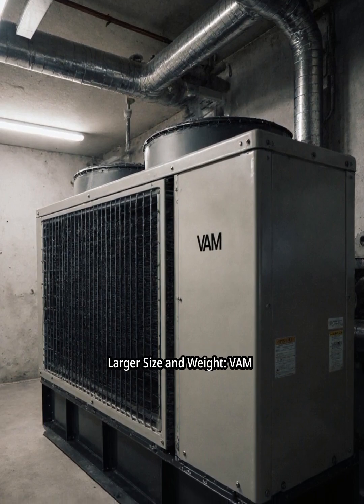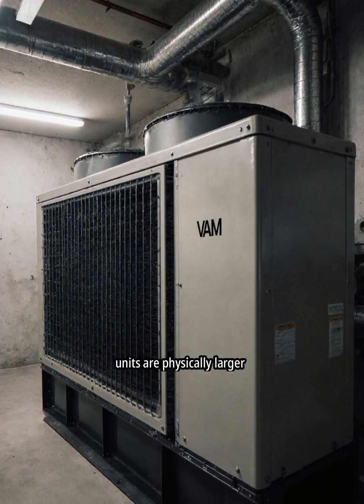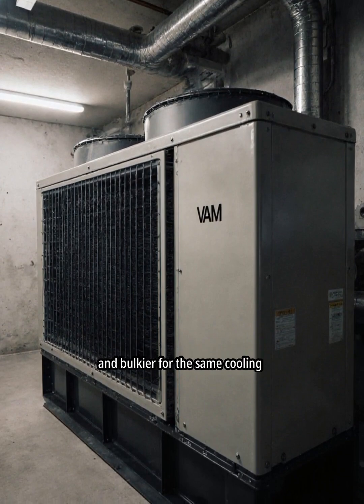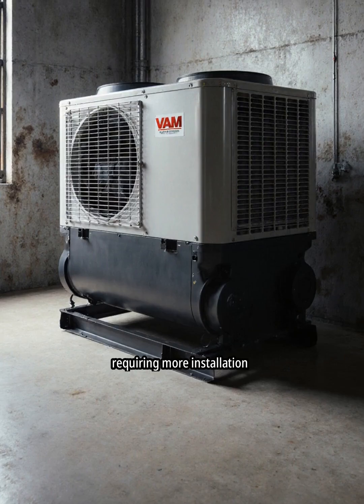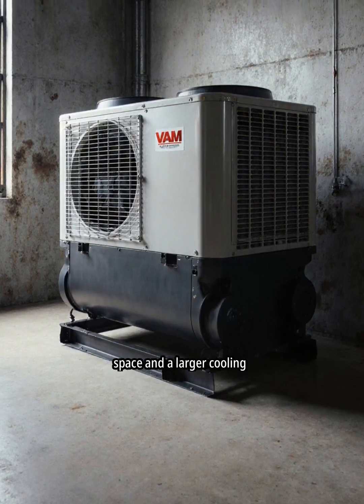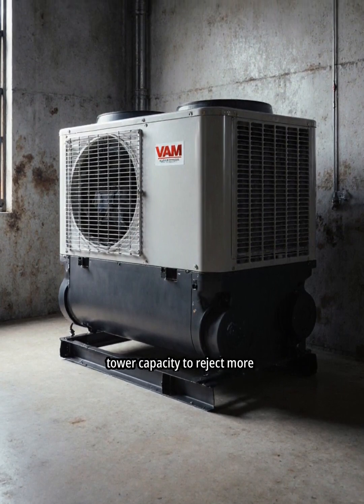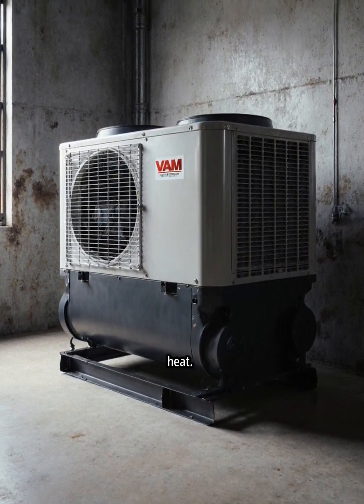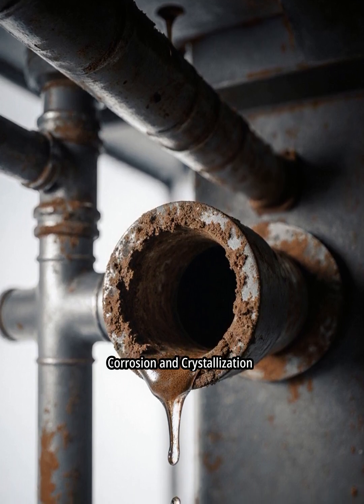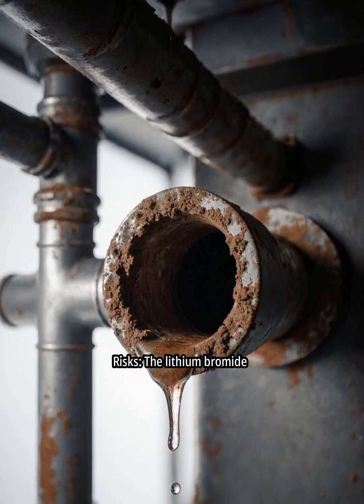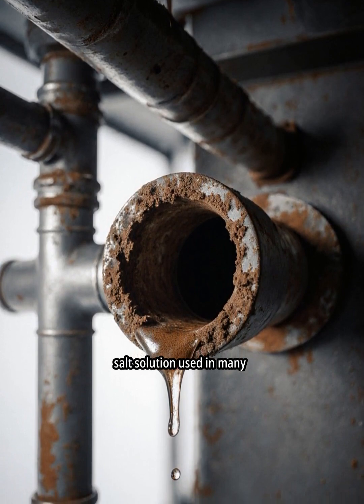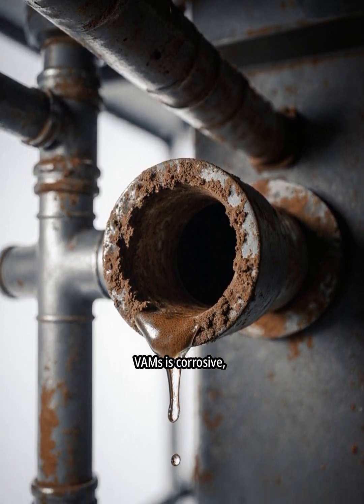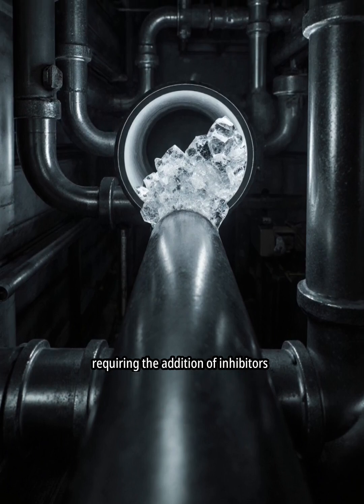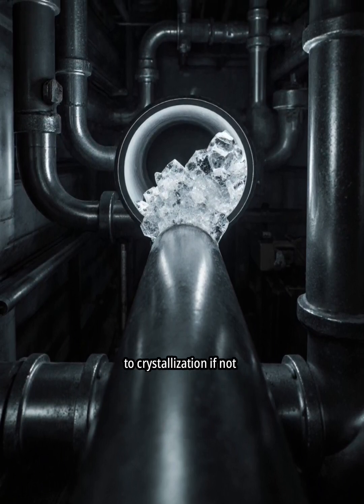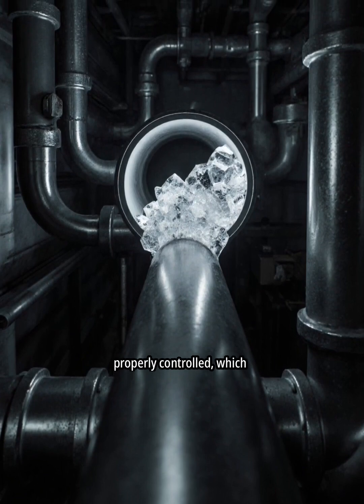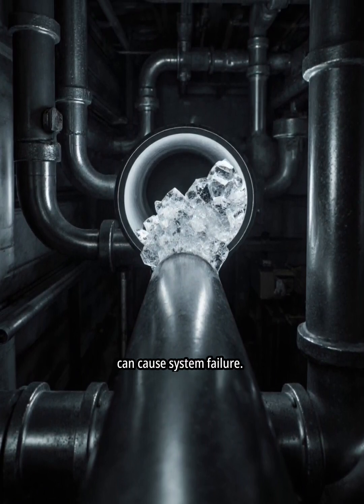Larger size and weight. VAM units are physically larger and bulkier for the same cooling capacity, requiring more installation space and a larger cooling tower capacity to reject more heat. Corrosion and crystallization risks. The lithium bromide salt solution used in many VAMs is corrosive, requiring the addition of inhibitors and making the system prone to crystallization if not properly controlled, which can cause system failure.